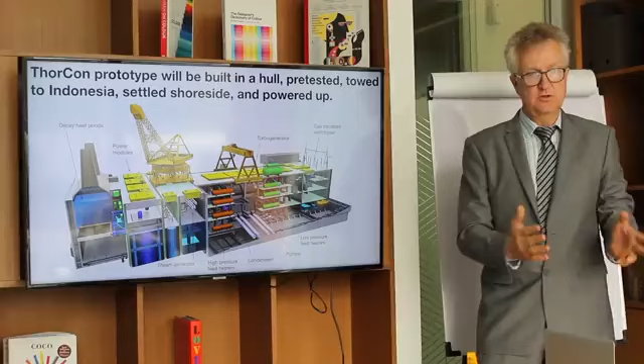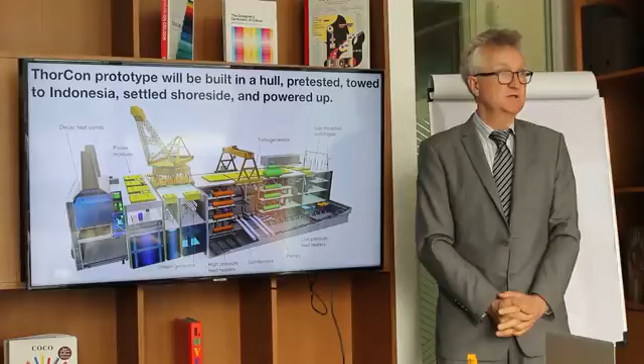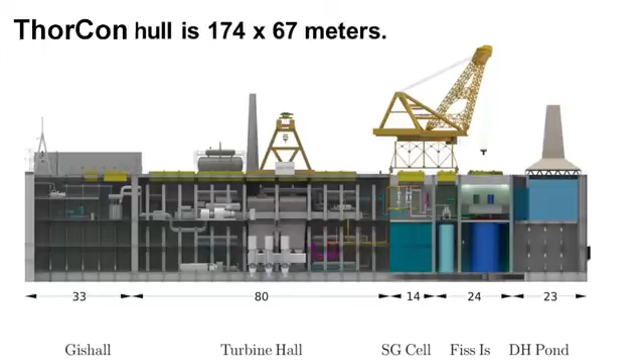You're parked right near the shore, and you're going to have an overhead transmission line. We also have an option for a subsea cable, so if you want to park 5 or 10 or 20 kilometers offshore, that's perfectly feasible. If you're going to park a long way offshore—for example, we looked at one site in Europe between London and Belgium, where we would have to go 50 to 80 kilometers—for that we probably want to go to high voltage DC, which is something you can also put in as an option into the switchgear yard.